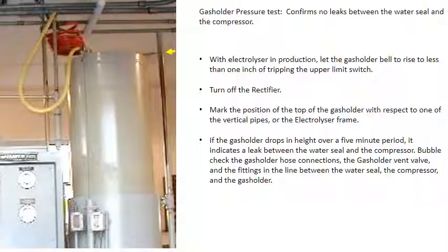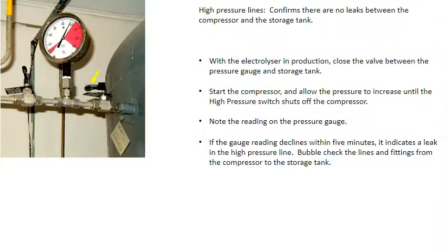The gas holder pressure test confirms no leaks between the water seal and the compressor. With the electrolyzer in production, let the gas holder bell rise to within an inch of tripping the upper limit switch. Turn off the rectifier. Mark the position of the gas holder with respect to one of the vertical pipes or the electrolyzer frame. If the gas holder drops in height over a 5-minute period, it indicates a leak between the water seal and the compressor. Bubble check the hose connections, the vent valves, the fittings in the line between the water seal, the compressor, and the gas holder.